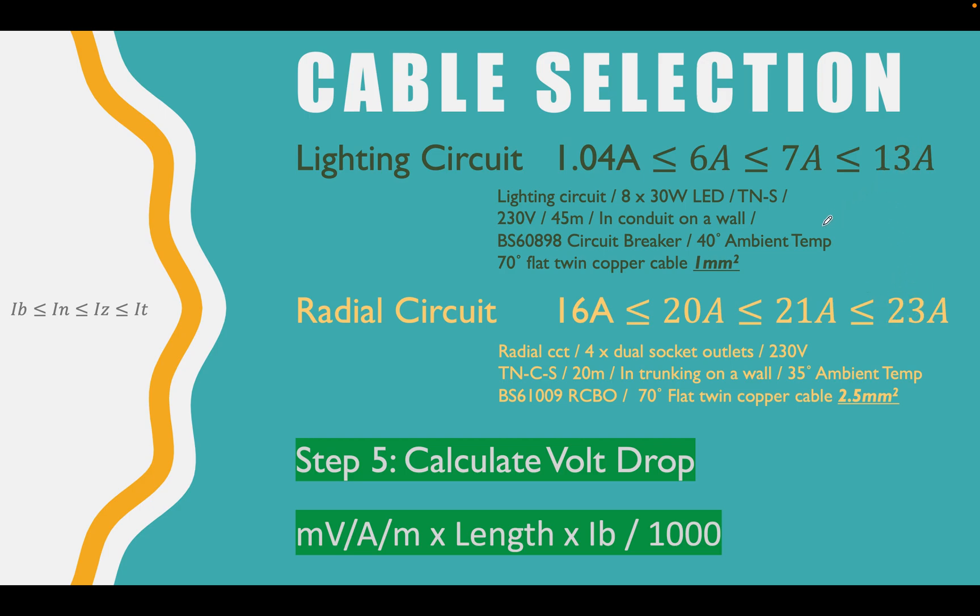Quick example of that, just so we understand what we've done. We selected a 1mm cable for our lighting circuit because we needed to select a cable that could take at least 7 amps, which we did. We went in that table and we selected 1mm, because 1mm could take 13 amps. So that's the tabulated value, 13 amps.